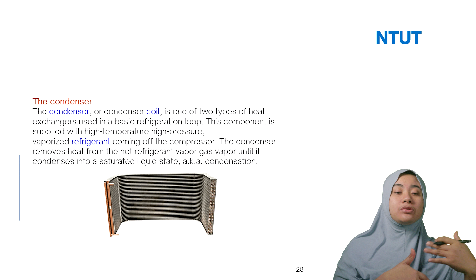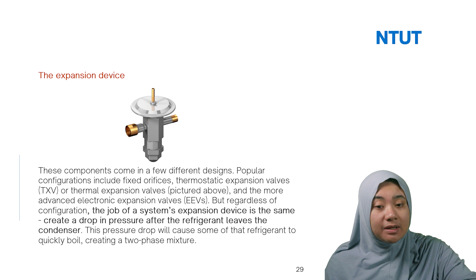So this is the expansion device. Actually, it's a Joule-Thomson or isenthalpic process, because the refrigerant expands from the high pressure to the low pressure. This pressure drop causes some of the refrigerant to boil quickly, so it creates a two-phase mixture. Then we have the evaporator, where the two-phase mixture becomes one phase. The evaporator is the second heat exchanger after the condenser in the standard refrigeration cycle, used to absorb the heat. The refrigerant enters the evaporator as a low temperature liquid at low pressure, and then the fan forces air across the evaporator's fins, cooling the air by absorbing heat from the space into the refrigerant.